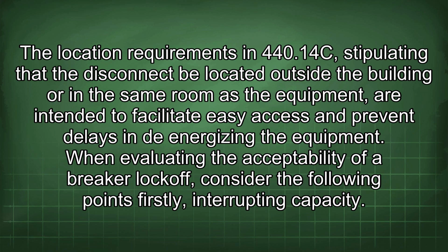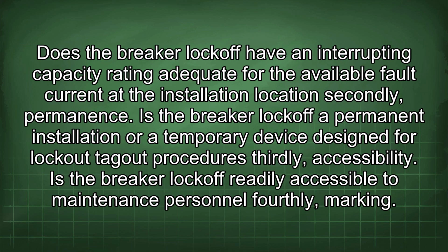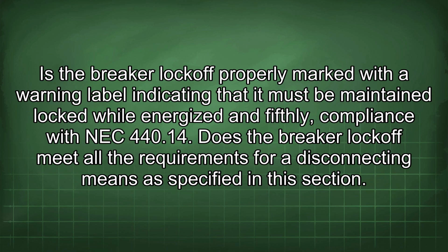When evaluating the acceptability of a breaker lockoff, consider the following points. Firstly, interrupting capacity. Does the breaker lockoff have an interrupting capacity rating adequate for the available fault current at the installation location? Secondly, permanence. Is the breaker lockoff a permanent installation or a temporary device designed for lockout tagout procedures? Thirdly, accessibility. Is the breaker lockoff readily accessible to maintenance personnel? Fourthly, marking. Is the breaker lockoff properly marked with a warning label indicating that it must be maintained locked while energized? And fifthly, compliance with NEC 440.14. Does the breaker lockoff meet all the requirements for a disconnecting means as specified in this section?